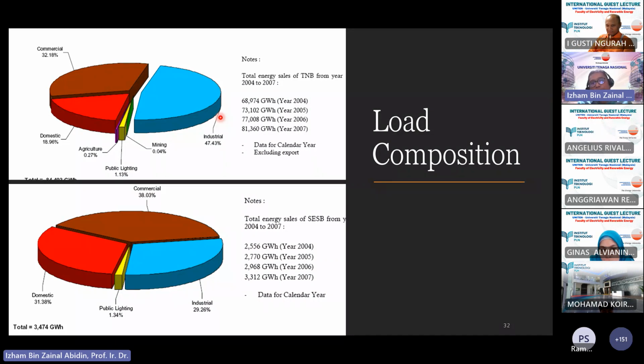If they go beyond this power factor point, they can be penalized by TNB because they'll be taking extra reactive power from the grid. Going back to when we talked about generators, this relates to the field current being generated by the generators. If it takes too much, the field current is overloaded, and damage to the generator is more expensive than installing a capacitor bank.